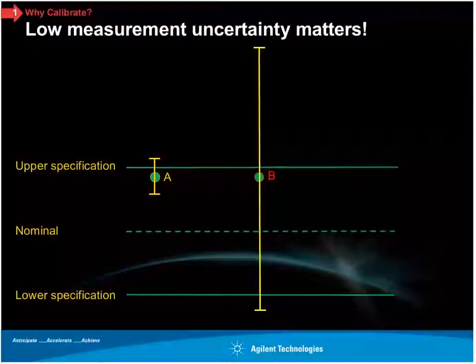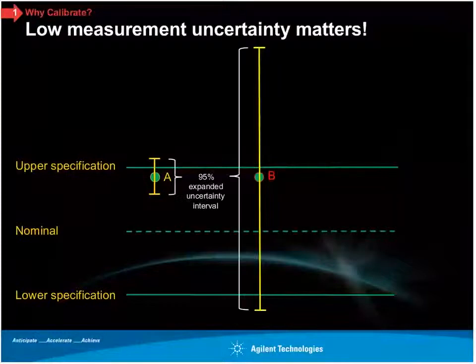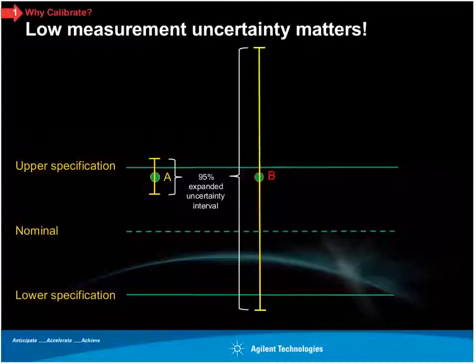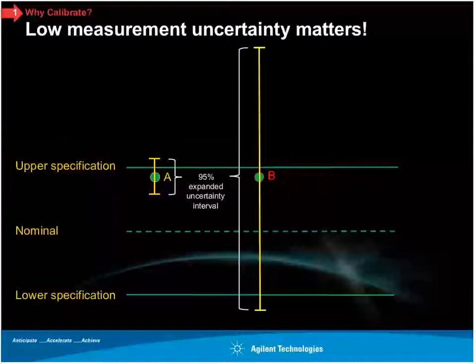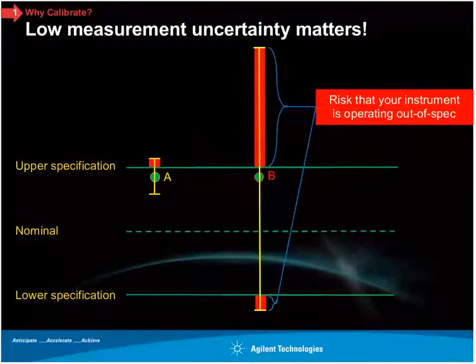So here, I'm showing 2 different intervals of measurement uncertainty, and you could think of these as standard deviations, and in fact, that's what they are. So if you were to do statistics, that would be where 95% of a population would fall. And just to bring that home, what we're really saying is those areas in red represent the probability that your instrument could really be out of spec.